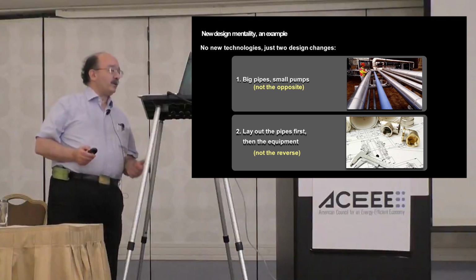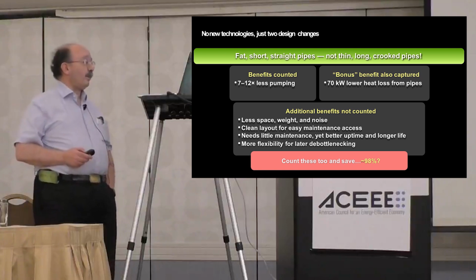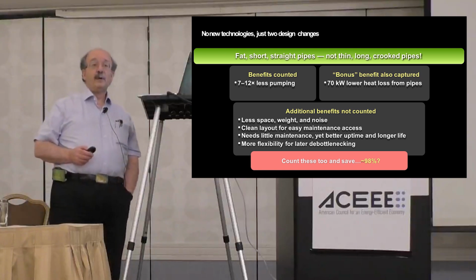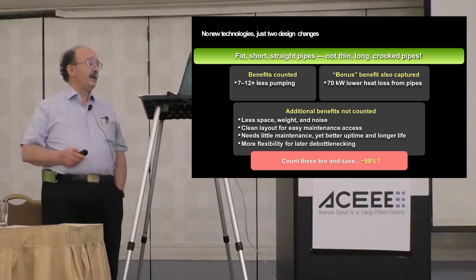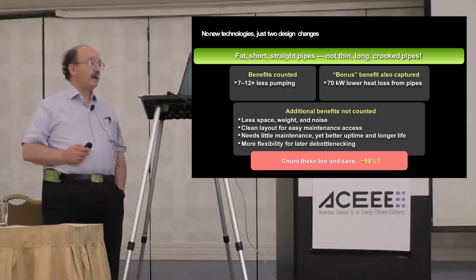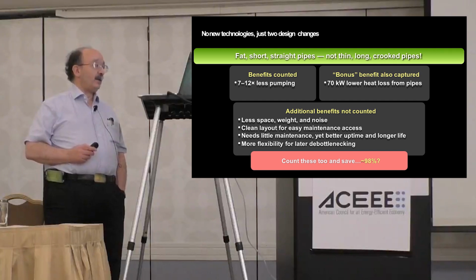In a Dutch industrial pumping loop case, this approach cut pumping energy by 7 to 12-fold with lower capital costs. With the free bonus, it also saved 70 kilowatts of heat loss with a 2-month payback, because short, straight pipes were easier to insulate than long, crooked pipes.